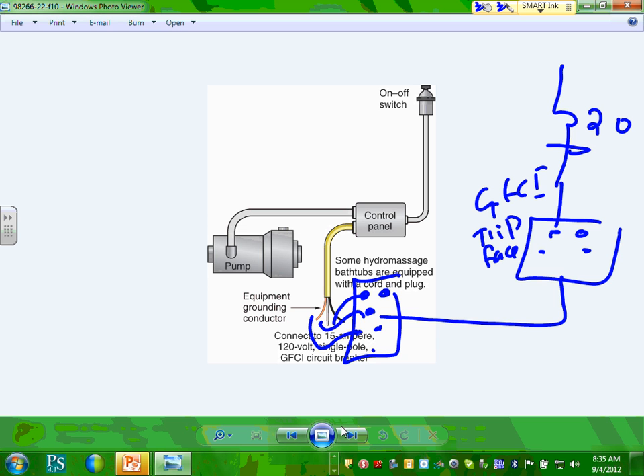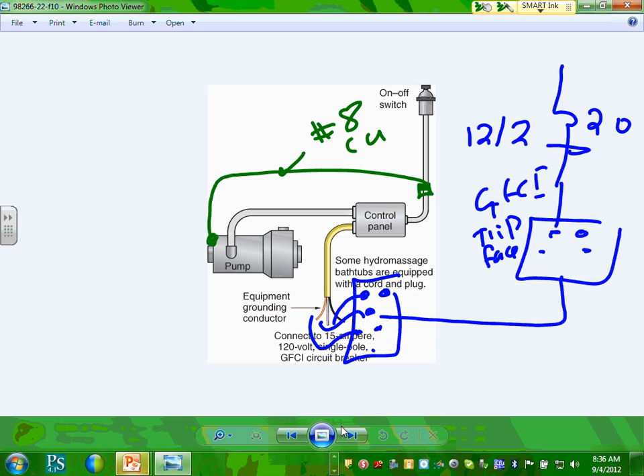And what do you bring here? You bring a 12-2 with a ground, of course. And then you have to grab a controller panel, and then you grab a bonding conductor from here and tie that bonding conductor to the frame, and that will be your number 8 copper bonding conductor. That's exactly how we do it. This is for the hydromassage bathtub. Absolutely. Any questions, guys? See how easy that is? Now you guys are master electricians. No question asked, you can jump in and wire. Really not a whole lot to it.